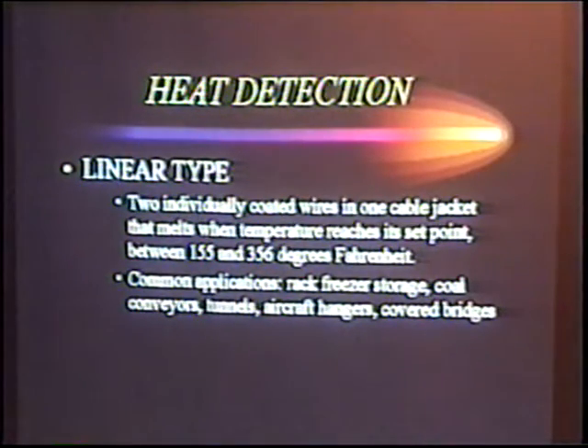There are a couple of different types of linear type detection out there. Probably the best known one is called ProtectoWire. We also have Alarm Line, which is a nice product. But really, linear type detection is a cable with a jacket. Inside this cable, you have a couple of individually twisted wires. The wires themselves are individually insulated. At its set temperature, typically between 155 and 356 degrees, the insulation coating of these wires melts, the two wires touch together, and you create a dead short. And that's how the system works.